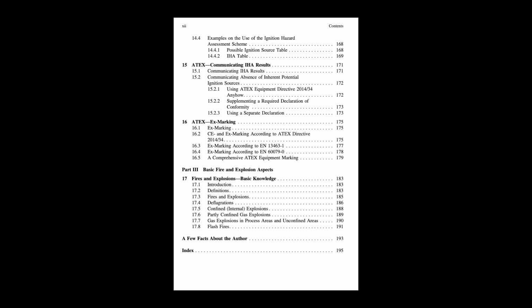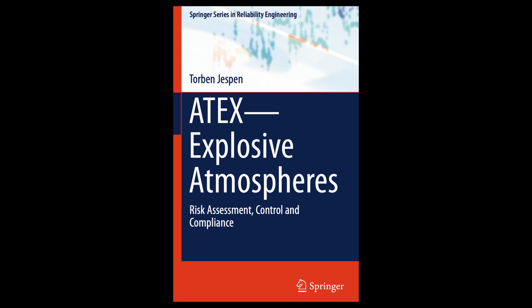Okay, let's shift gears slightly to hazardous area classification, or zoning. What's the underlying goal of this whole zoning system? The fundamental purpose of zoning is to minimize the probability of having an explosive atmosphere and an effective ignition source present at the same time. Matching the risk to the protection.